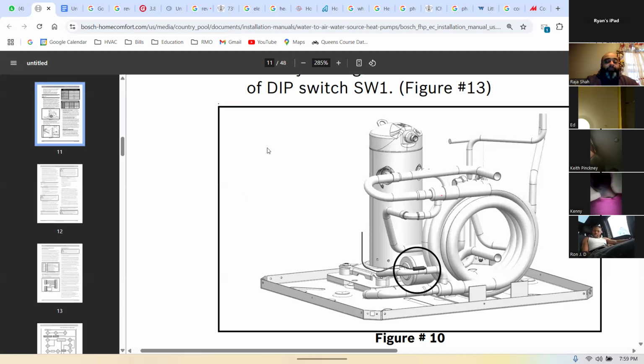So fellas, we were talking about a water source heat pump. Now you got that compressor here, and you got the coil within a coil over here. What does that mean, a coil within a coil? So inside of this coil, you have another coil that you don't see. You're gonna have that water running through in one direction, and you got the refrigerant flowing through in another direction. That's the condenser water - remember, where's the condenser water come from, Ron?